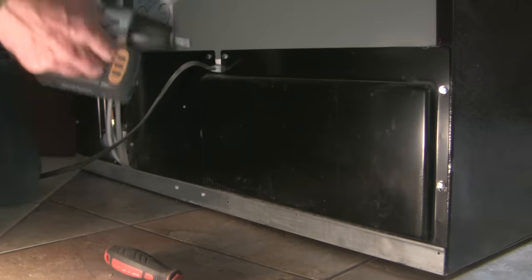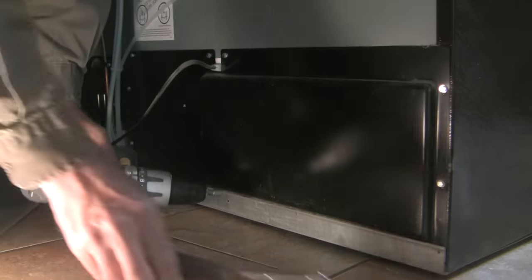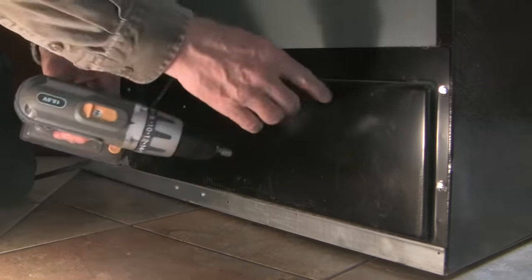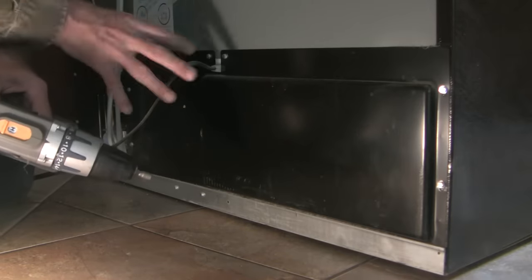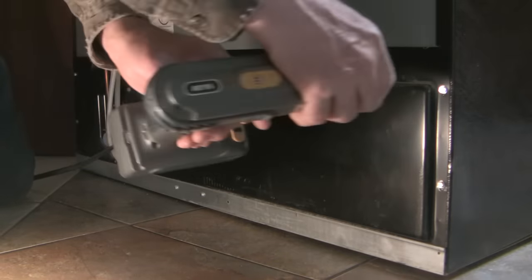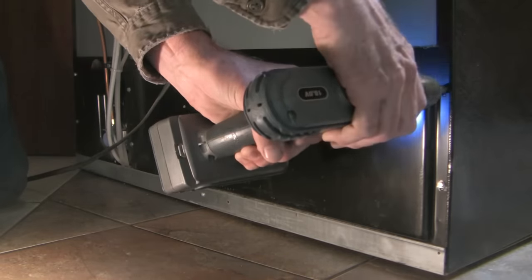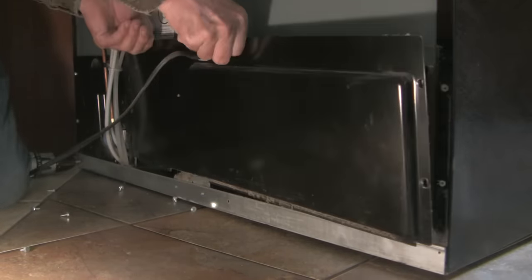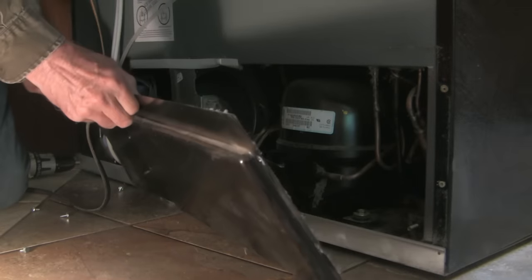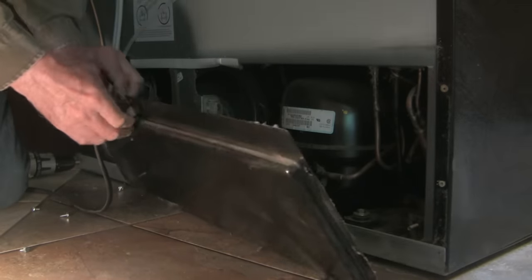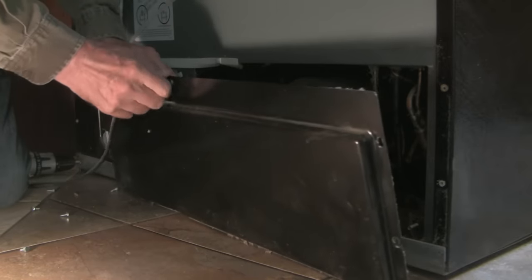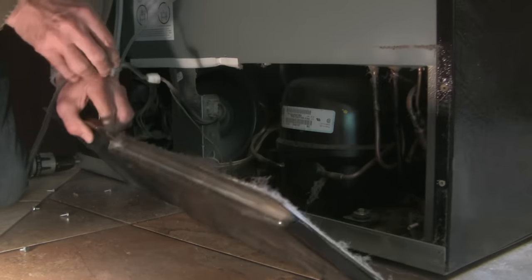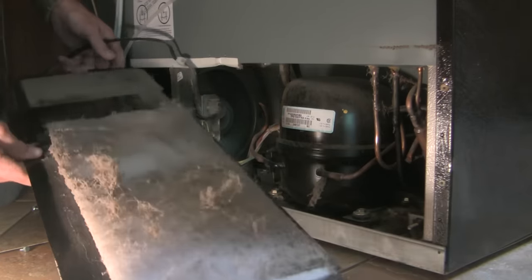So I'm going to get some compressed air in there and blow it out and we'll see if that does the trick. I'd like to get to the condenser fan to try and clean it better from behind, so I'm going to take off these screws and get this panel out of the way. Wow, look at all that dust.